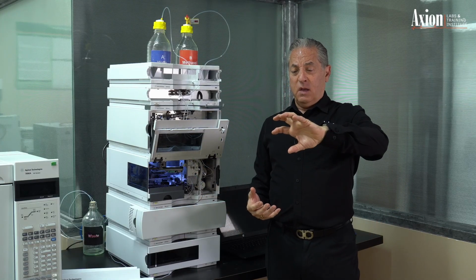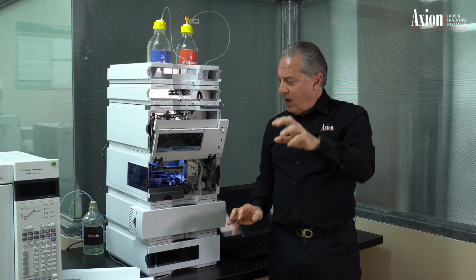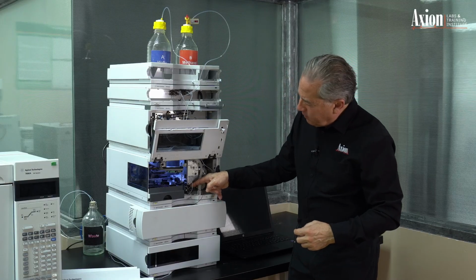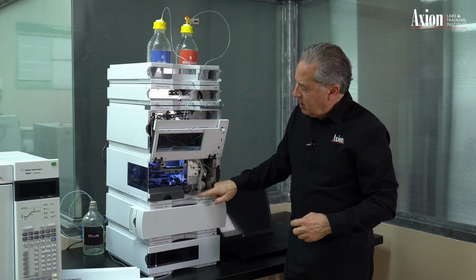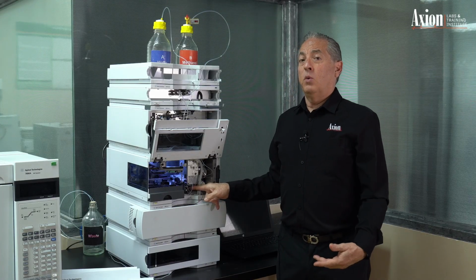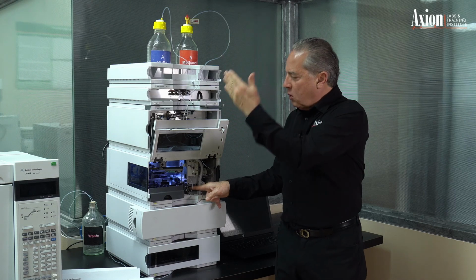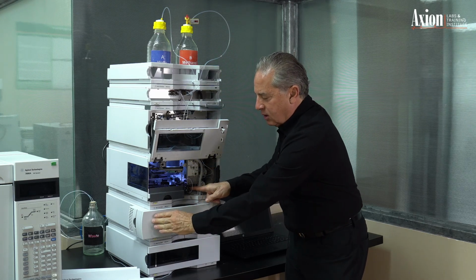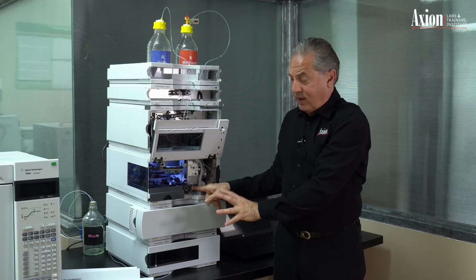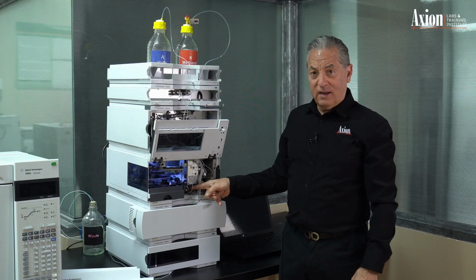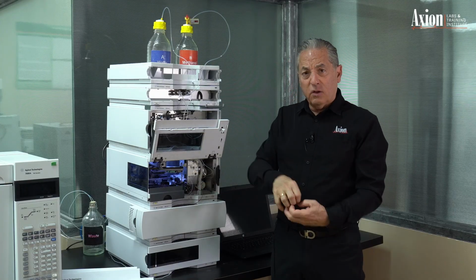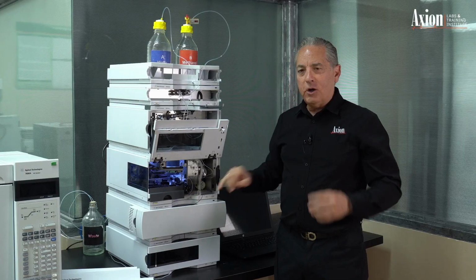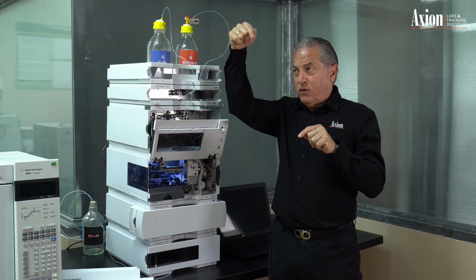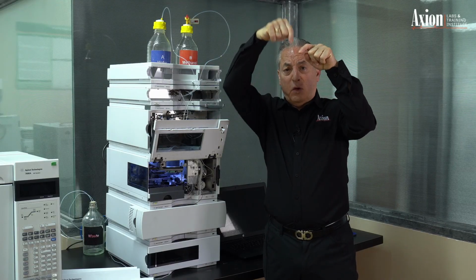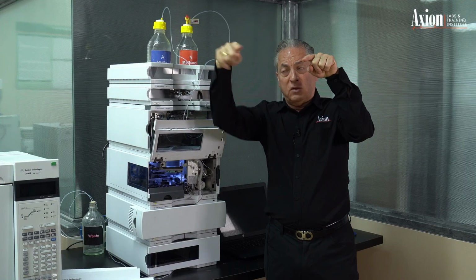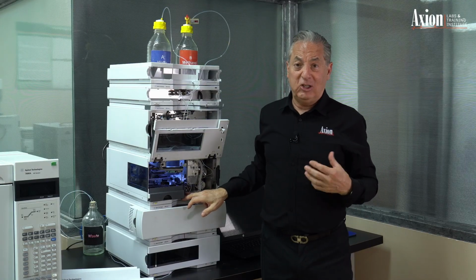We start by taking the autosampler offline, rotating the valve. And by rotating the valve, we're going to take the high pressure flow, go to the valve, and we're going to connect right next door, and this is going to go to the column. So in that mode, what's called the bypass mode, or the load mode, it allows us to take high pressure flow, go to the valve, bypass the autosampler, and go onto the column, and then the detector. That keeps the column happy, keeps the detector happy, nice stable flow. So during that time, we could then lift up the needle, go to the vial, draw a sample up, reconnect, and when it reconnects, all we got to do is rotate the valve just a sixth of a turn to connect the flow coming in, going through the autosampler. So imagine, flow comes in, it could go straight to the column, or it could go through the autosampler and then to the column. That's what the injection valve does.